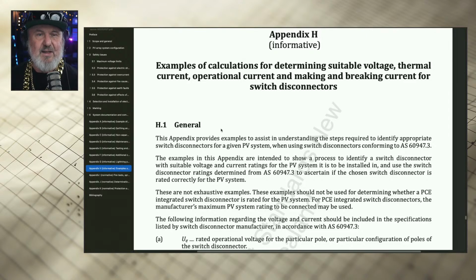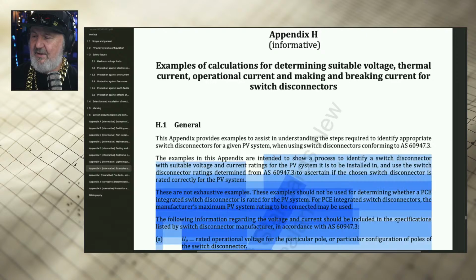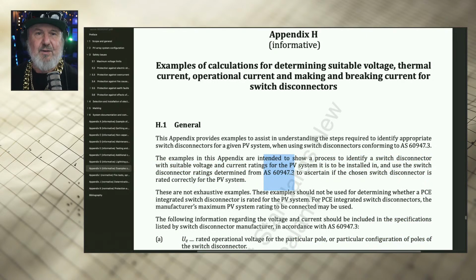Now, these are all covered in the test standard for, in the case of DC switch disconnectors, an Australian adoption of the IEC standard 60947.3, if you're really into numbers. And there it is, AS 60947.3. And if you're using circuit breakers, it's .2.